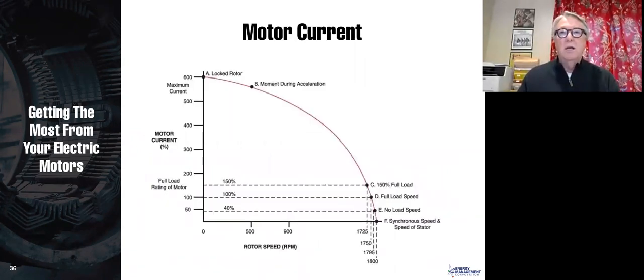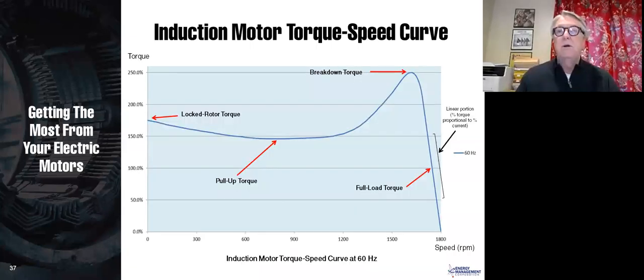Here's your motor current. Now we're talking about locked rotor current, not inrush, and you'll notice that it starts around 600%, but then as the motor comes up to speed, it comes down here, and right in here, we're going to talk about this more. I'm going to say that the current is proportional to the torque. Now, I'll tell you I lied, and in a few minutes we'll get a little bit more specific about that. But I would say really at least from 50% load to 150% load, you're operating in this range in here, and the percentage current is pretty close to the percentage torque. So if you want to know how much that motor's loaded, meaning how much torque the motor's providing, you just measure the current, and that provides you with a pretty good indication.